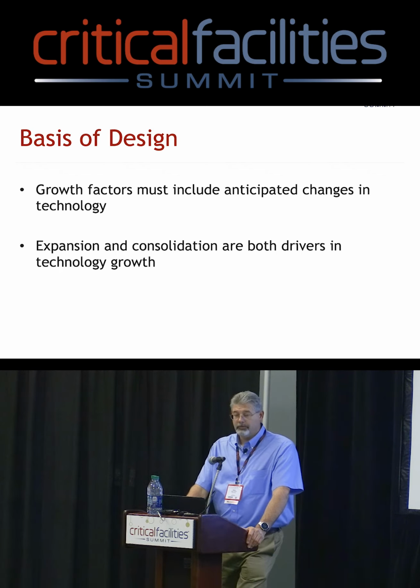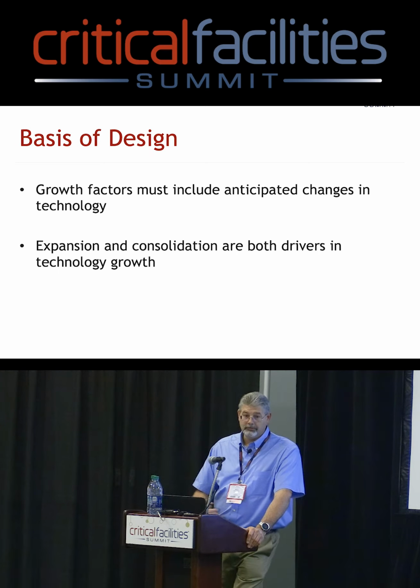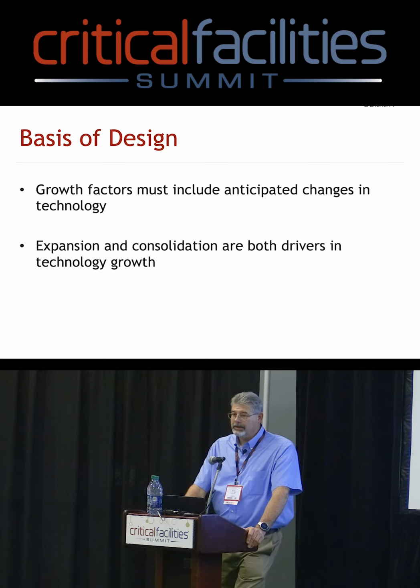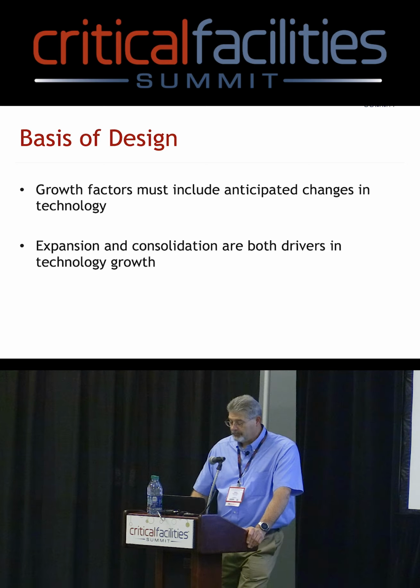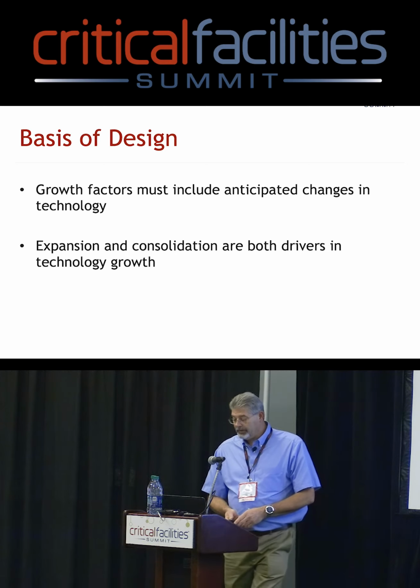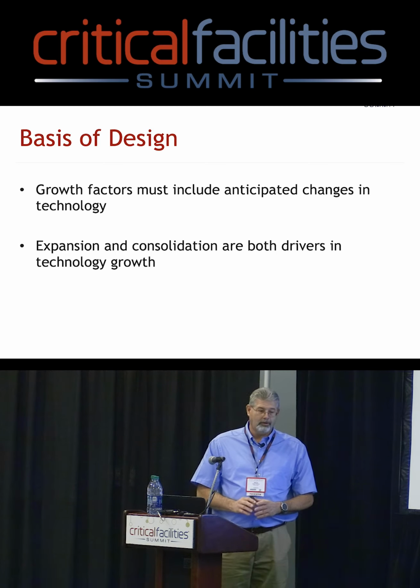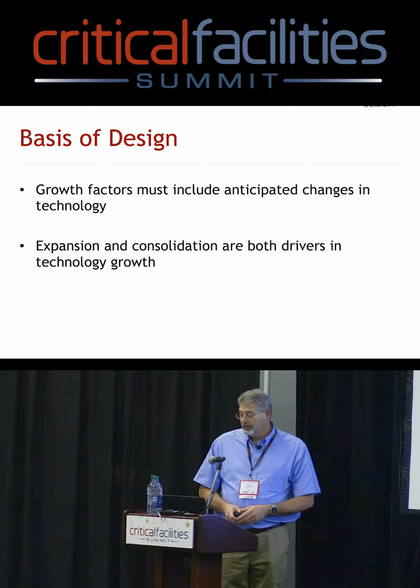Are you going to be into some of the larger switches that have airflow that is side to side instead of front to back? That requires a rack all of its own type, and it really, really screws with your hot aisle, cold aisle configuration. Increases and decreases in environmental requirements across platforms are almost never uniform.